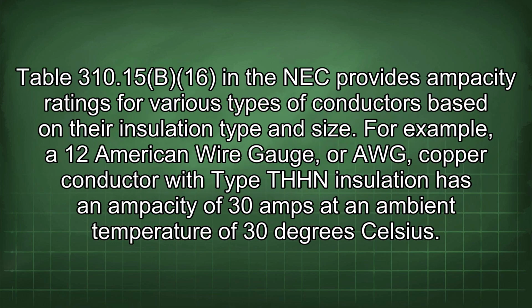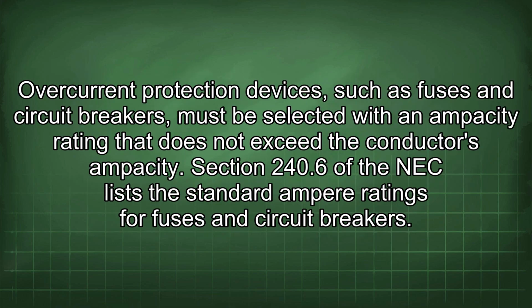Table 310.15(B)(16) in the NEC provides ampacity ratings for various types of conductors based on their insulation type and size. For example, a 12 American wire gauge, or AWG, copper conductor with type THHN insulation has an ampacity of 30 amps at an ambient temperature of 30 degrees Celsius. Overcurrent protection devices, such as fuses and circuit breakers, must be selected with an ampacity rating that does not exceed the conductor's ampacity. Section 240.6 of the NEC lists the standard ampere ratings for fuses and circuit breakers.